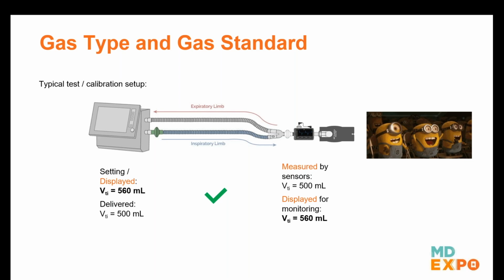Okay. What is ATP? Actual temperature and pressure. So that's what we're really measuring, right? Because the flow sensor doesn't care. It can be warm, it can be dry, it can be wet, it can be cold. It doesn't matter. It's going to measure the actual flow. It's just this convenience factor that has been built into ventilators that gives us all these other different gas standards. Again, match your gas type, match your gas standard, you're good to go.